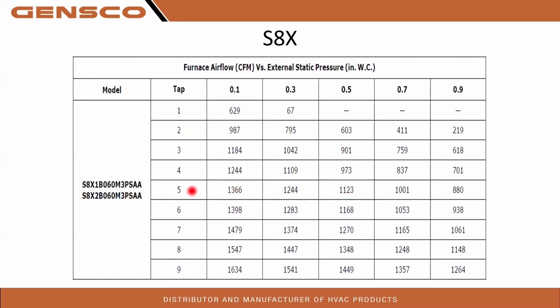So again, the good thing with the S8s and S9s, we can actually change these CFM settings on the fly, so we don't have to de-energize the system. Keep in mind, if you have a dip switch that you need to set, you're going to have to cycle power. You're going to have to kill the power, change your fan setting, and re-energize. And then, again, take your static pressure to see what your actual CFM is.